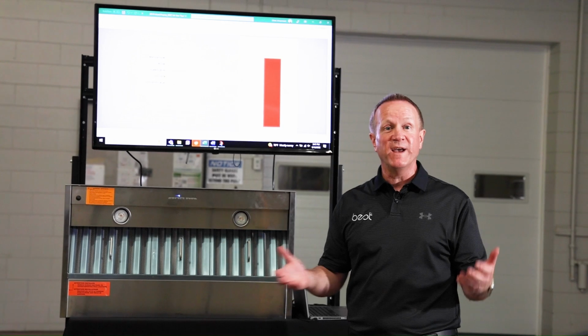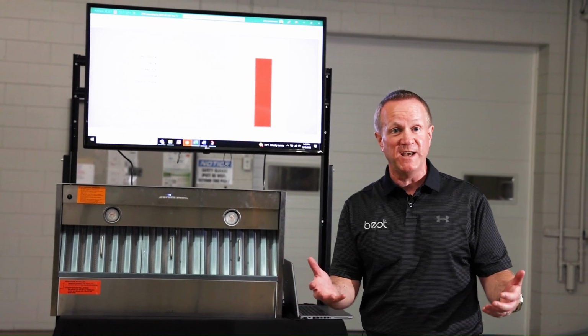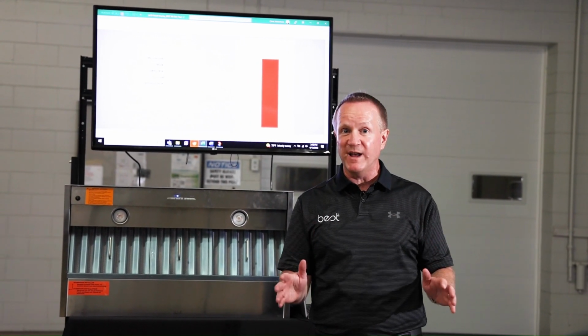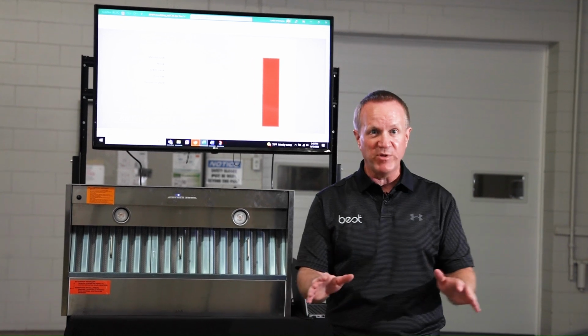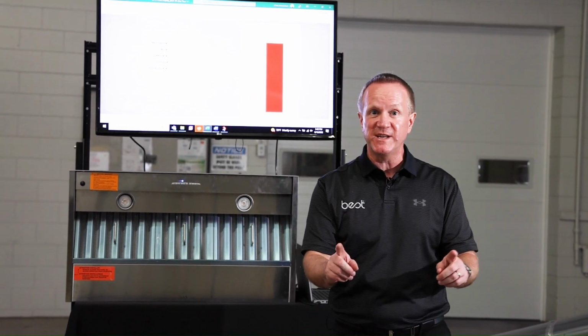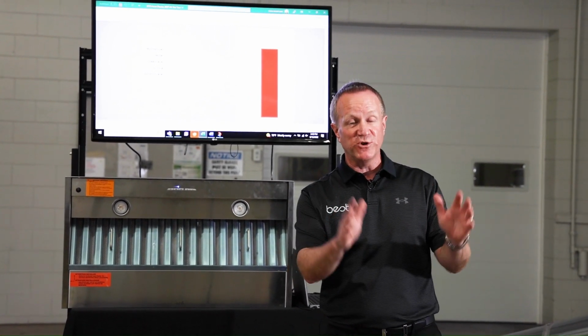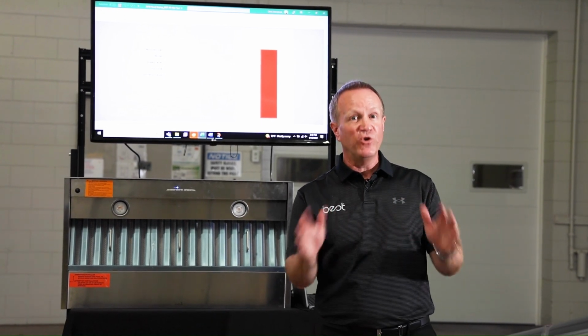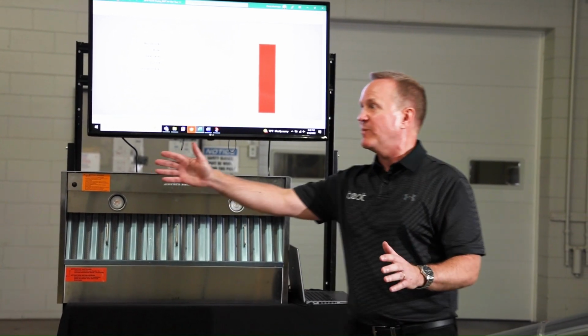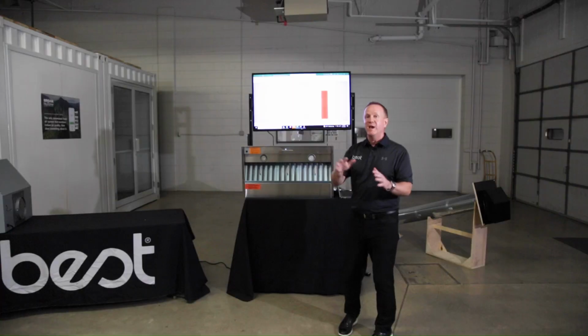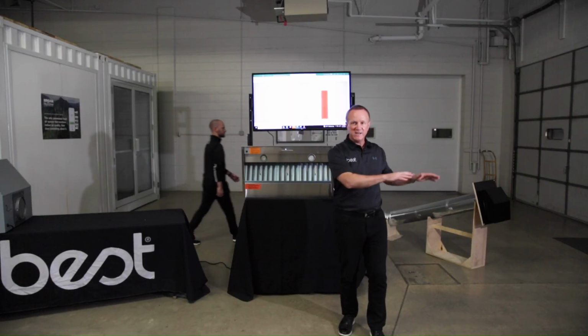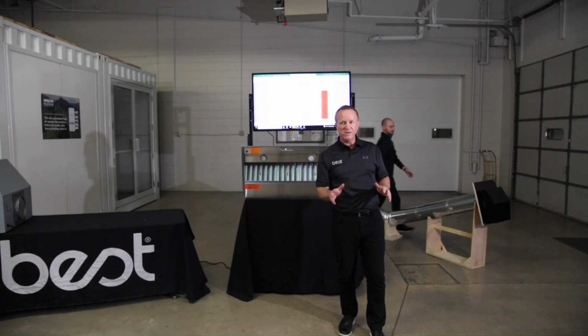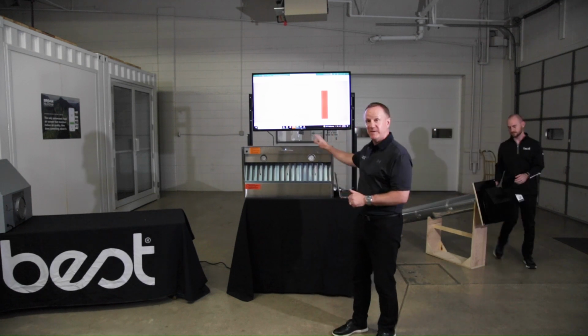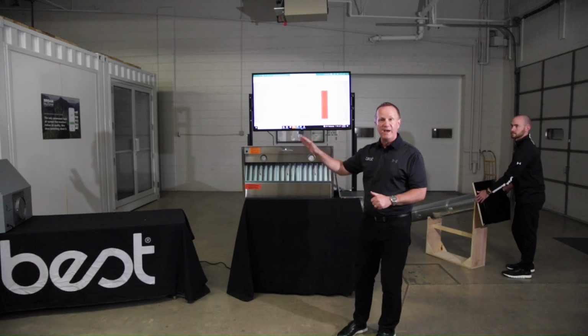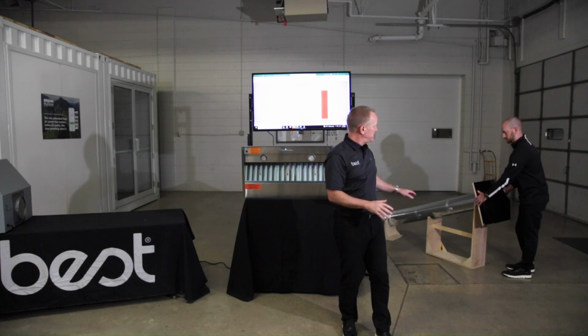So we're now performing at 655 CFM. So you've worked with your client, you've looked at their cooking application, and you've said 600 CFM is what you need, Mr. or Mrs. Client, to have good odor and smoke removal. So my colleague is now going to come around and we're actually going to disassemble all of our ducting. So again, we're at 655 roughly at full installation.